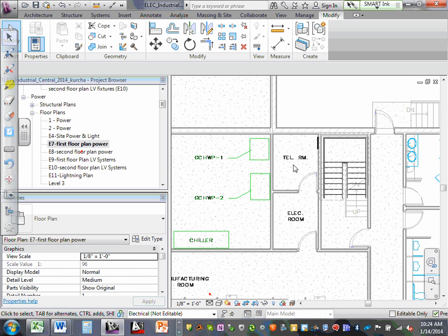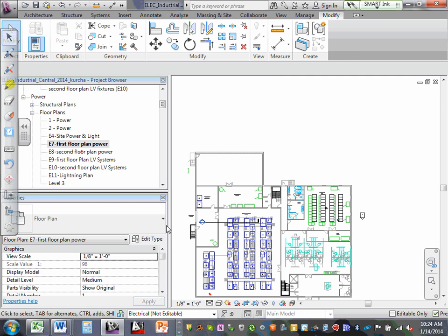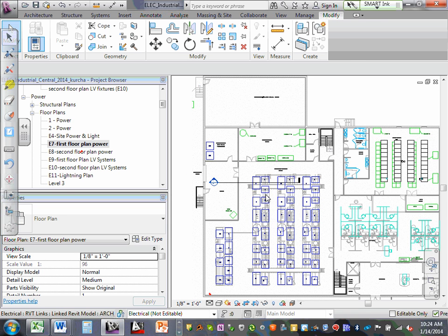So, with that said, your devices again are connected to the fire alarm system via what's called a signaling line circuit. Also, your detection devices are. And a signaling line circuit, with the equipment that we represent, we can have up to 159 detectors on a single pair of wires. In addition to that, on that same pair of wires, 159 modules. Oh, what's a module? Well, I've got to monitor flow switches and tamper switches, and I've got to monitor that pre-action system panel. I've got to monitor that valve assembly. I've got to shut down air handling units, I've got to recall elevators. Okay, so modules provide inputs and outputs in the fire alarm system.